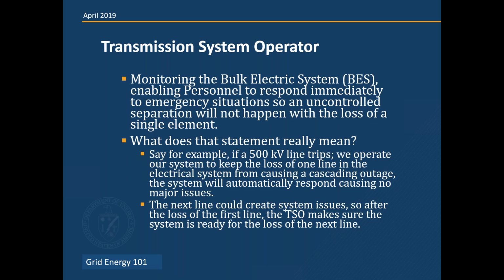Monitoring the bulk electric system, enabling personnel to respond immediately to emergency situations so that uncontrolled separation will not happen with the loss of a single element. So what does that really mean? Say, for example, if we had a 500 kV line that trips, we operate our system to keep the loss of one line in the electrical system from causing a cascading outage or causing the system to go unstable. Especially if the next line could create that stability issue, the TSO makes sure that the system is ready for the next line loss. Next slide, please.